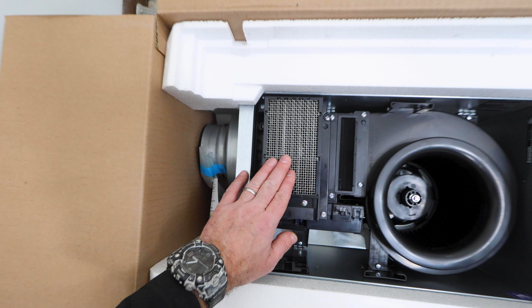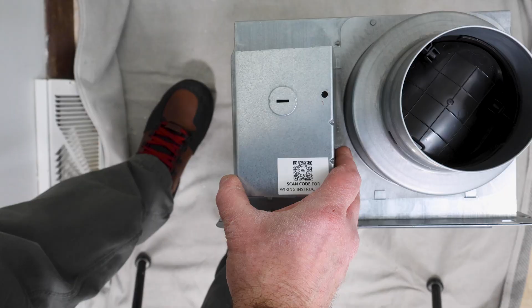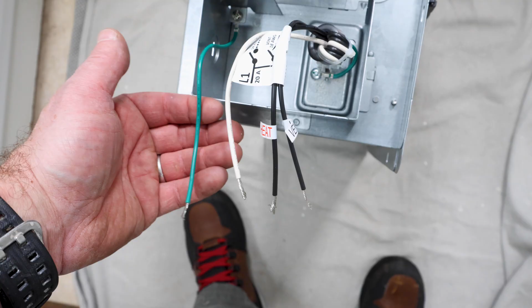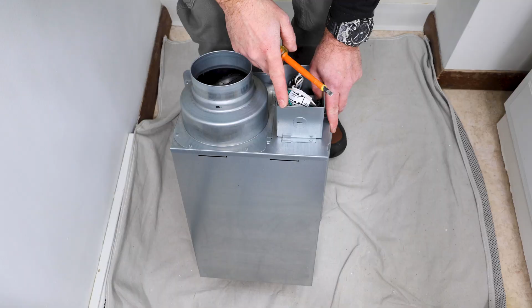A few things about this fan. It has a Flex Z fast bracket, which I'll show you how to install. The heater is right next to the fan unit, and you can adjust the CFM just by the flip of a switch. So we can go from 80 to 110 CFM real quick. One big mistake people make is with the electrical. So there's a ground, neutral, and 2 hot wires. The mistake is not using a Romex cable connector. So I take the knockout out and I put the cable connector in, and then you run the wire through that.